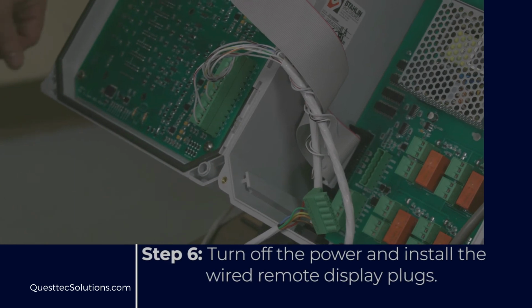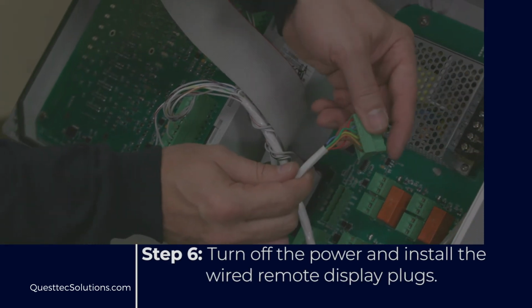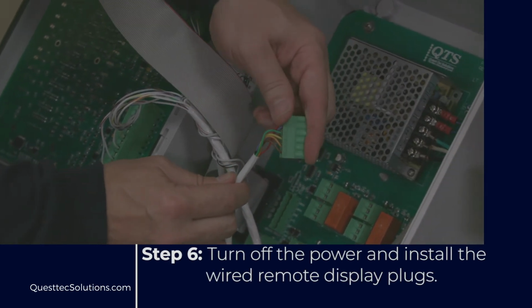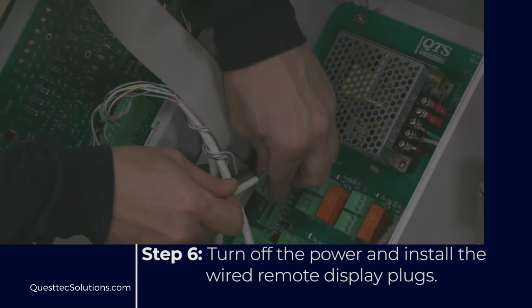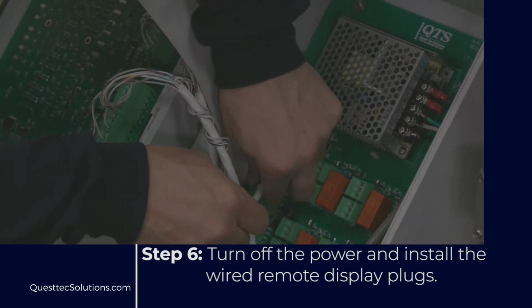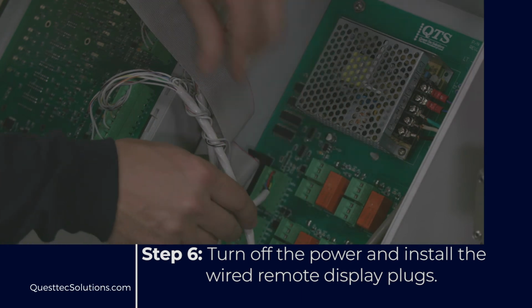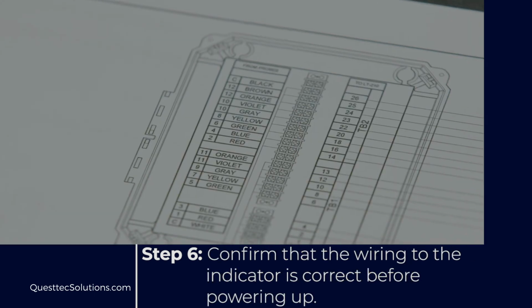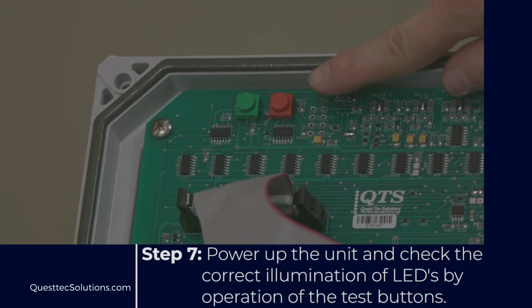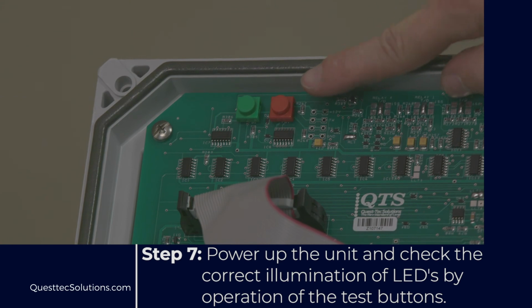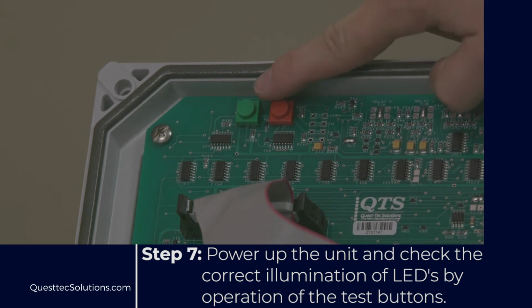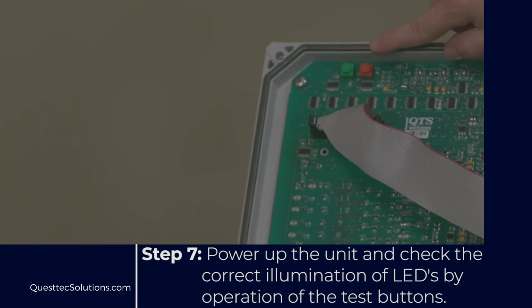Step 6. Turn off the power and install the wired remote display plugs if used. To prevent permanent damage to the discriminator PCB, confirm that the wiring to the indicator is correct before powering up. Step 7. Power up the unit and check the correct illumination of LEDs by operation of the green and red test buttons.